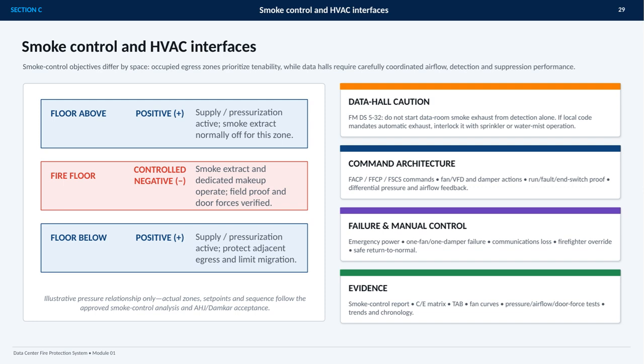A key data hall caution is that smoke exhaust should not start from detection alone under FM guidance. Where local code requires automatic exhaust, it should be interlocked with sprinkler or water mist operation. Finally, the command architecture must prove fan, damper, pressure, and airflow status, while planning for failures, manual firefighter control, emergency power, and documented testing evidence.